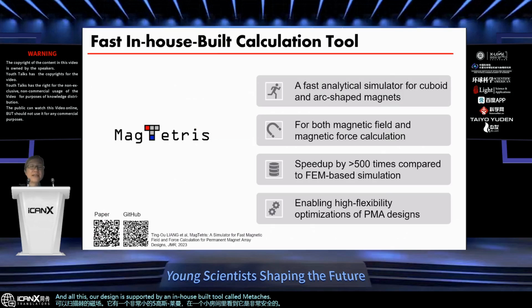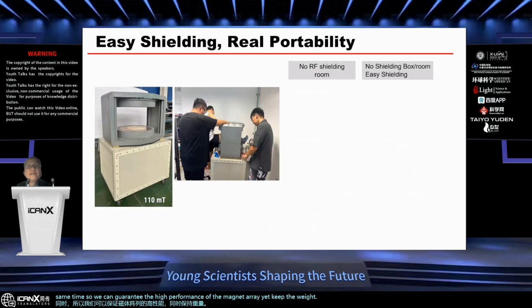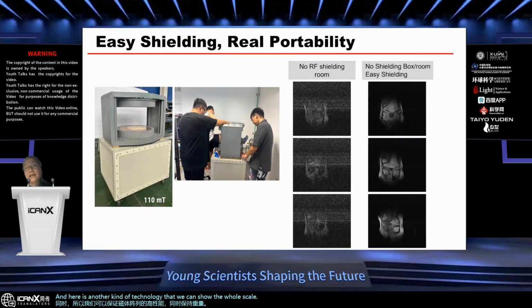It has fast calculation. It can afford the calculation of multi-millions of magnets at the same time. So we can guarantee the high performance of the magnet array, yet keep the weight light. And here shows another technology of ours, where we can shield the whole scanner easily. If you compare the two columns right here, one is without our shielding techniques and the other one is with them. The photo here shows exactly how a scan is done.